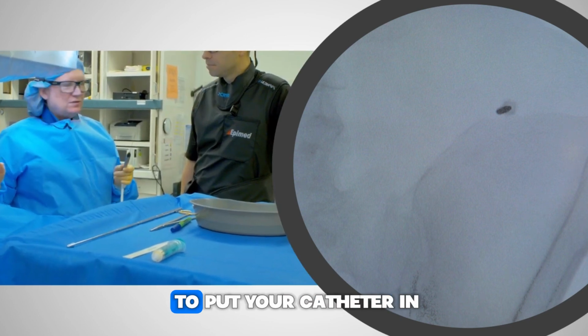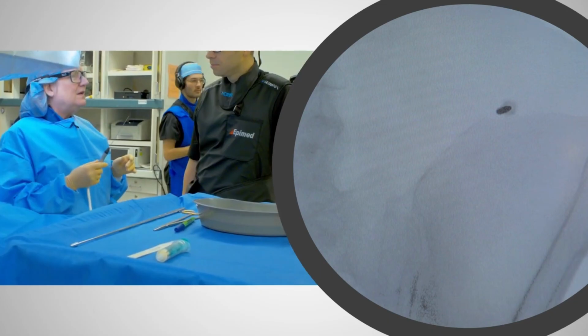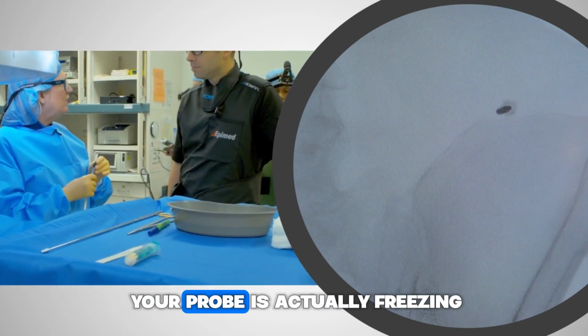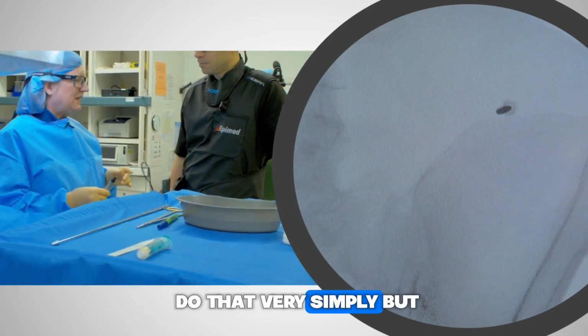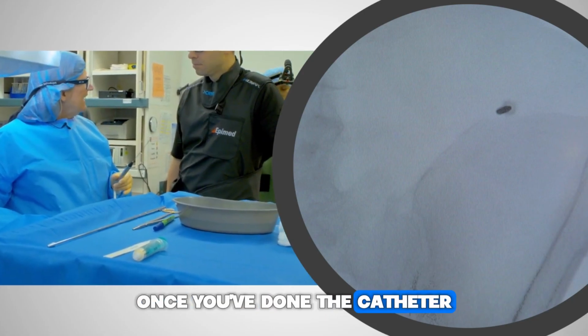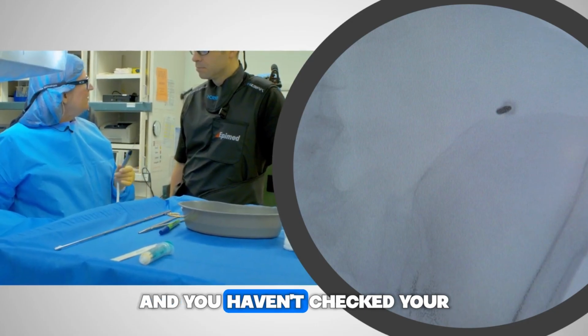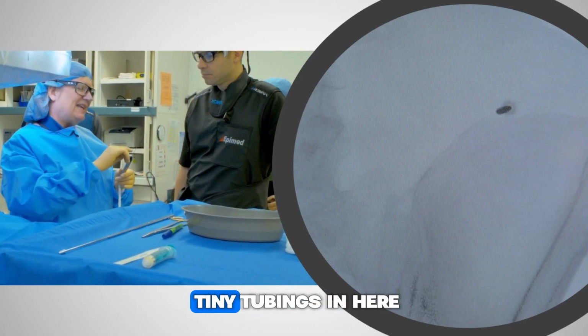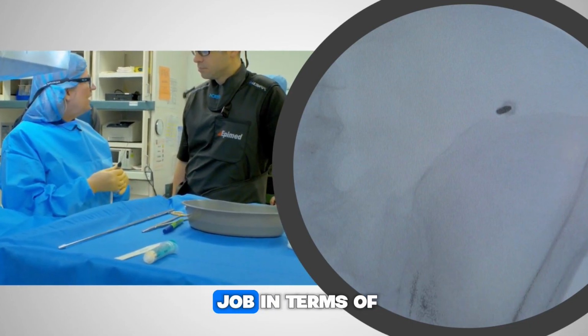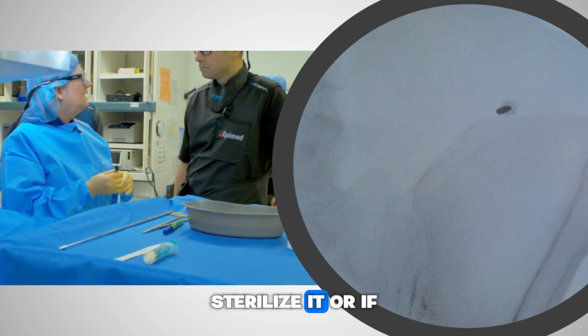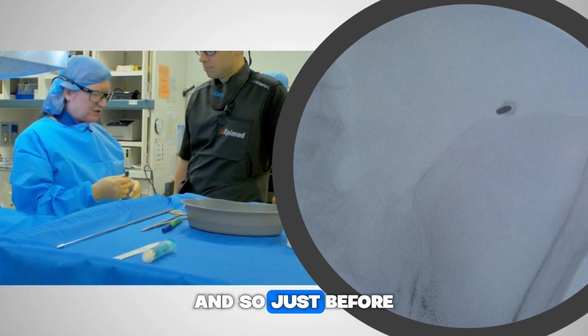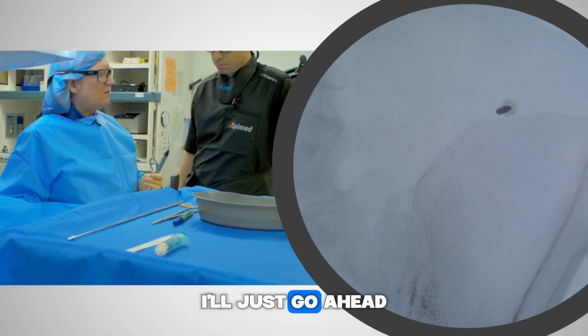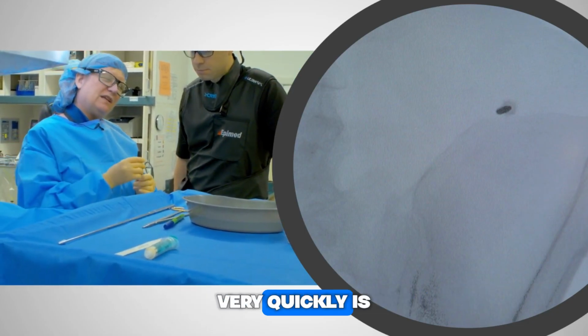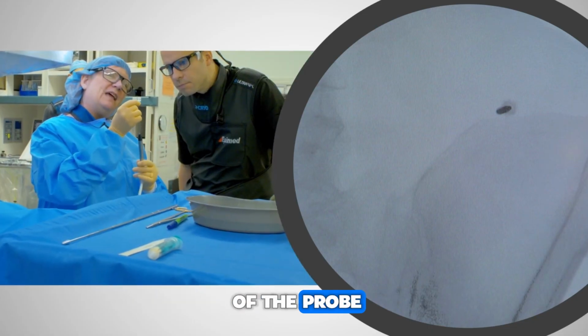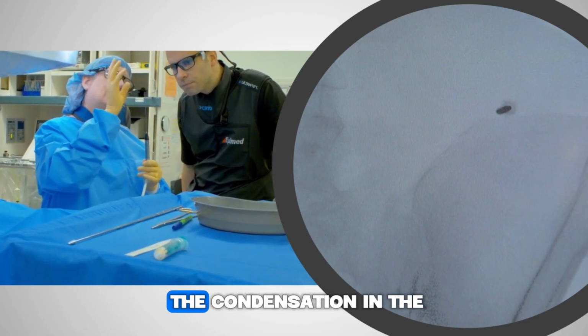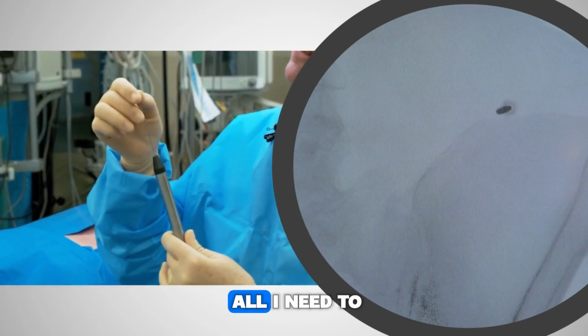Before you actually go to put your catheter in, I think it's a wise thing to do to make sure that your probe is actually freezing. You can do that very simply, and I like to do that before the catheter is in place, because once you've done the catheter, you've sort of committed the patient, and you haven't checked to see that your equipment's actually working. These have got tiny, tiny tubings in here, and if somebody didn't do a good job in terms of trying to sterilize it, or if there's wet gas in the system, there'll be a problem. So just before I put my catheter in, I'll step on this briefly, and what you'll start to see very quickly is the frost occurring right on the edge of the probe. If there's a lot of moisture in the air, you'll actually see the condensation in the air. That's all I need to know right there.